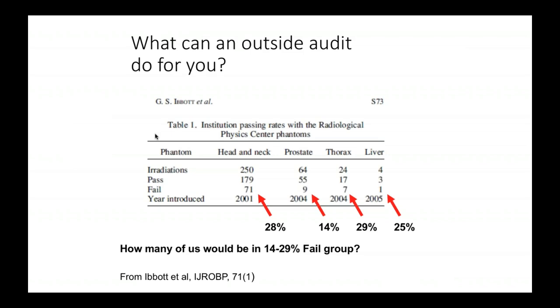This slide shows data from an audit. A study published in the Red Journal sent out a phantom to different institutions across the United States with a given treatment plan, asked them to deliver that plan to the phantom with a dosimeter in it, and then measured the dose to see whether the prescribed dose was actually what was delivered. They checked for variation across centers, and obviously some centers failed — this is just to illustrate that this is a problem present even in the United States.